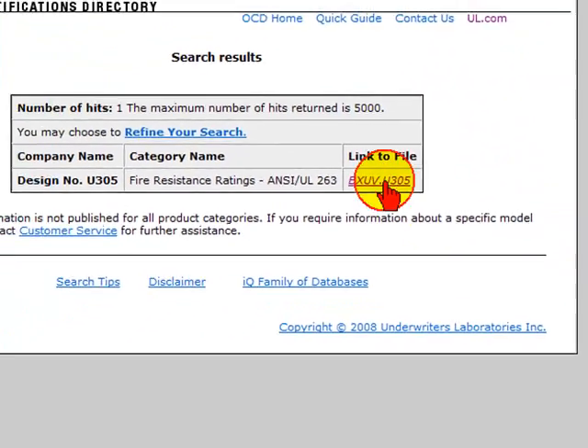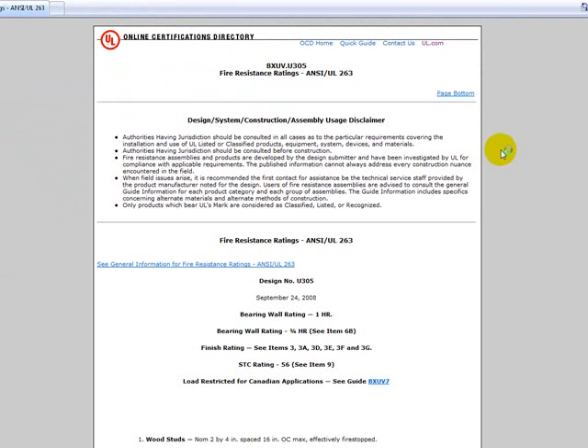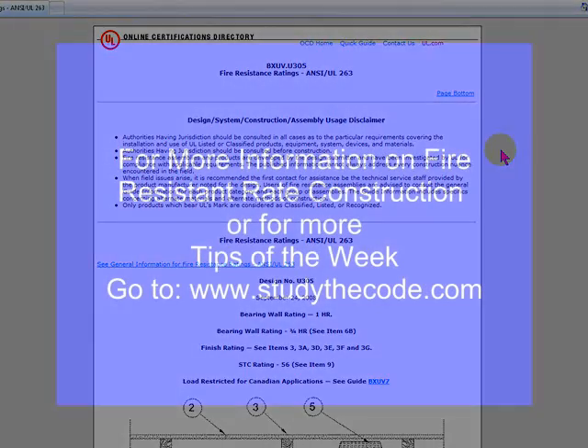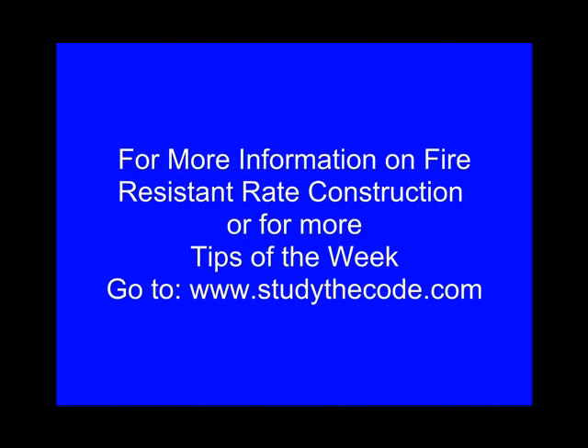We click on this link and the entire design can be viewed online or it can be printed out for your review and use. Please note this design, as well as all UL designs, gives very detailed information as to the name-brand materials to be used, as well as how the materials are to be installed. If this design criteria is not followed exactly as written, then the UL design will be invalid.